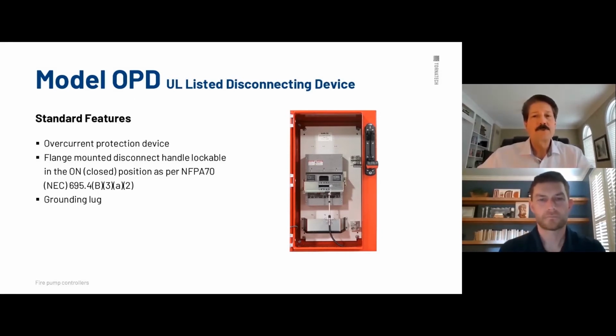We really don't run neutral for any particular reason because these units are sized based on horsepower and voltage of the motor, and those motors are 3-phase only. So there is really no need for a neutral, but sometimes we run into those requests by the local inspector, and it might be an electrical inspector who's your AHJ there. Just let us know.